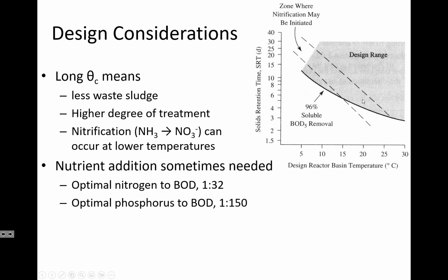Ironically, there are a handful of cases where there may be a limitation of either not enough nitrogen or not enough phosphorus in a wastewater treatment plant, where you're trying to remove one, but the other is a limiting factor. And so occasionally they'll have to add external nutrients into the aeration basin, and occasionally even BOD will be the limiting factor. And it's kind of interesting, there are a handful of wastewater treatment plants that keep bags of dog food on hand, and they'll just pour dog food into the aeration basin because that's the BOD that's required. If they've got more nitrogen and phosphorus than food available, they have to feed the microorganisms that are consuming the nutrients.